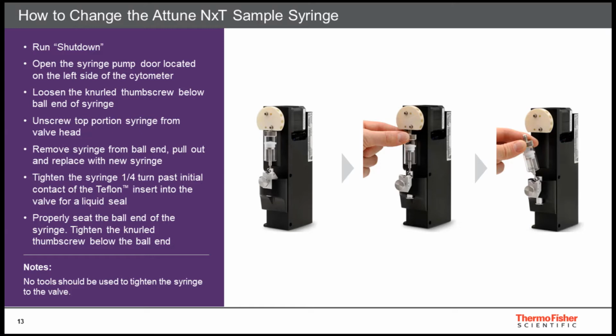Next, ensure the new syringe is not seized by pushing and pulling on the plunger before installation. Install the syringe and finger tightening should be enough. Do not use additional tools to tighten the syringe. Properly seat the ball end of the syringe in the plunger retention apparatus and tighten the thumb screw to secure the plunger end of the syringe. Again, finger tightening should be enough.